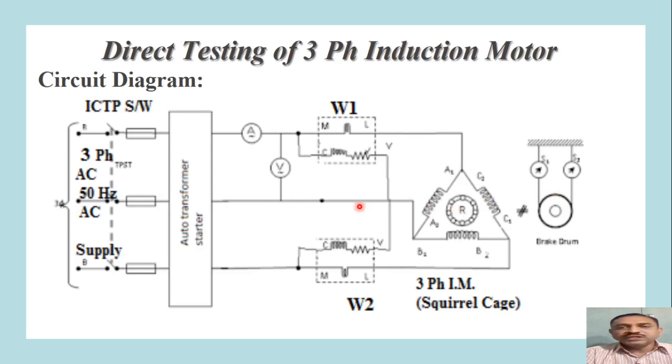We have to do the testing starting from no load, then we can gradually increase the load, maybe as per our requirement, that is 5% or 10%. We can operate the motor up to 100% and up to 110%. So a number of readings are required to be taken during these tests, and it will be a time consuming process. At the same time, we must take enough care to cool the brake drum, because when it is loaded, it will be heated because of the losses. So this care should be taken.